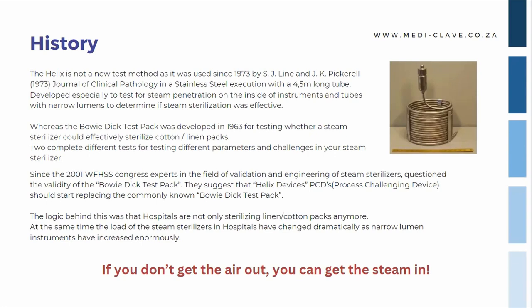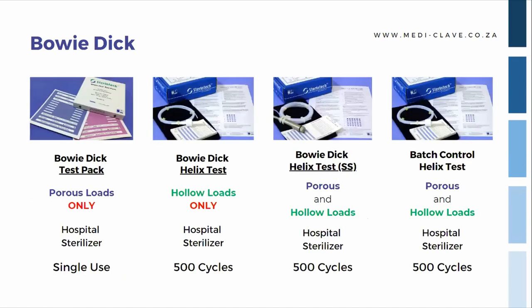So let's look. I'm going to work through each sterility assurance product, but I'm going to start with the Bowie-Dick test pack. And there are four different types. We all know the Bowie-Dick test pack. It's used in most of the hospitals in South Africa. It's for porous loads only. It's used in a hospital sterilizer and it's for single use.